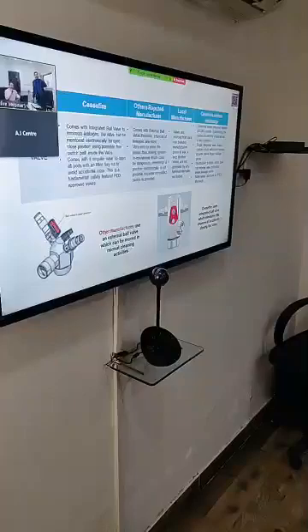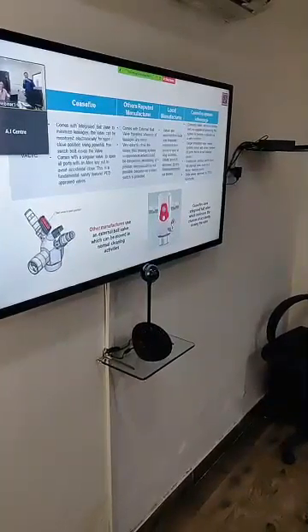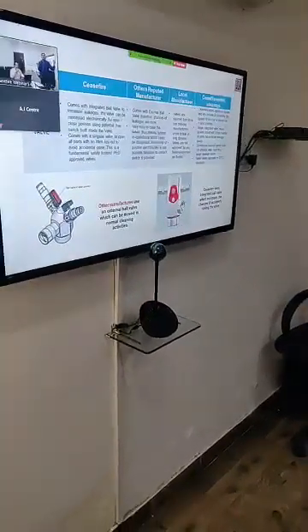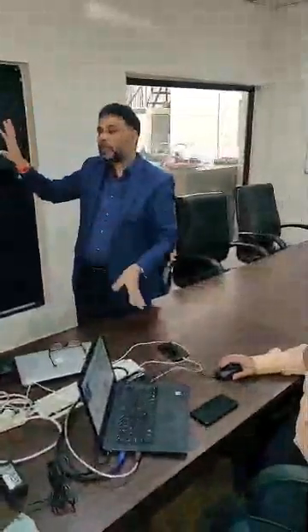Intentionally also, if somebody wants to do it, on the other side he can do it very easily. In our case, there are hindrances. Even if he is doing it, there is a reed switch which is coming out from the panel. So the moment the valve is closed, your reed switch, which has got a NO/NC relay, will start giving a signal to the panel, and the panel will start showing you the beeps, the trouble beep. That means your system is in a non-working condition.